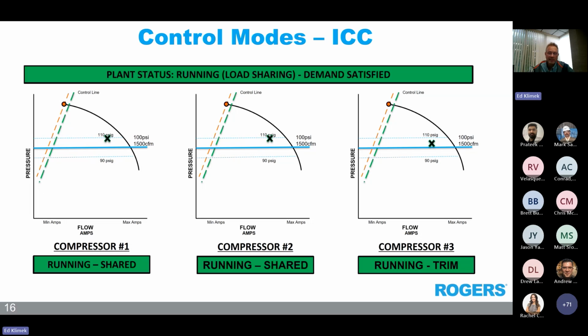So again, this animation really doesn't show a high system pressure situation, but if it did, all 3 compressors would throttle to their minimum operating points. And once all compressors are throttled to their minimum operating points, compressor number 3, or the trim machine in this example, would be marked for blow off and eventually shut down. And as the plant needs more air, it would bring on those additional machines again.